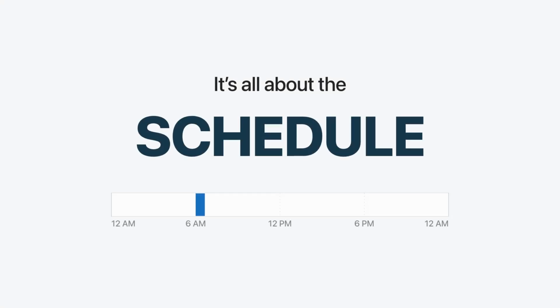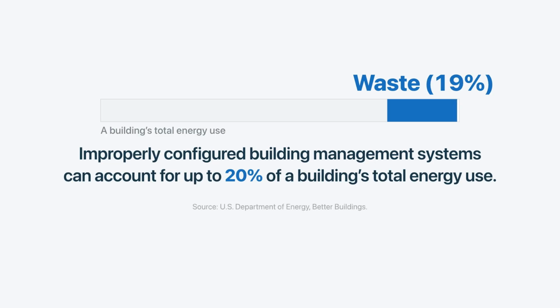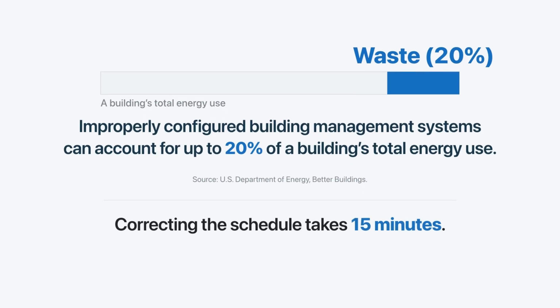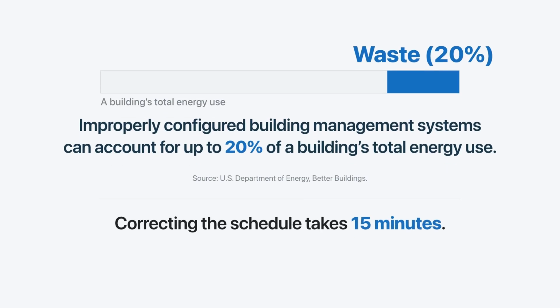The single most valuable 15 minutes you can spend in a commercial building is fixing the HVAC schedule. Not replacing equipment, not retrofitting anything, just correcting when the HVAC system actually runs. The Department of Energy estimates that improperly configured building management systems account for up to 20% of commercial building energy use. Much of that, in practice, is schedule drift.